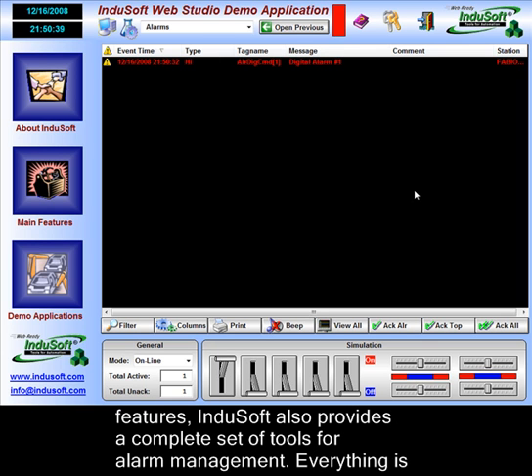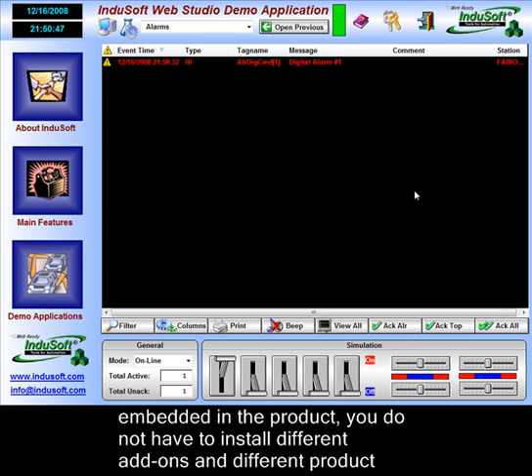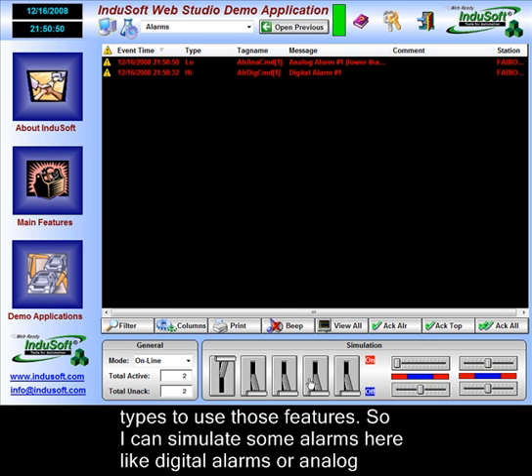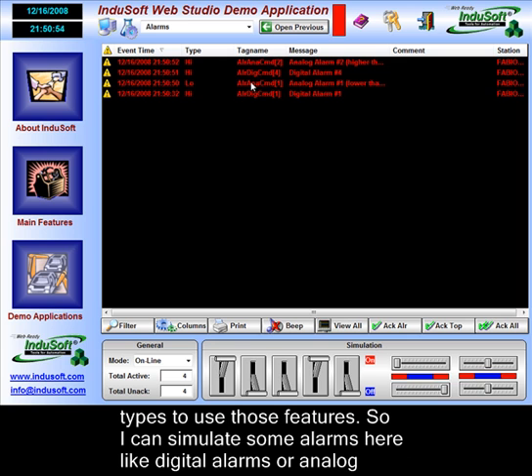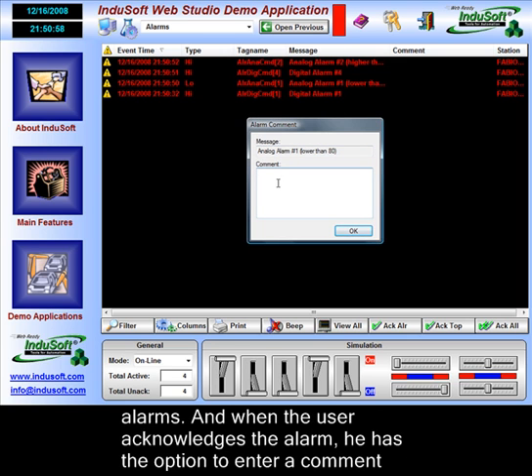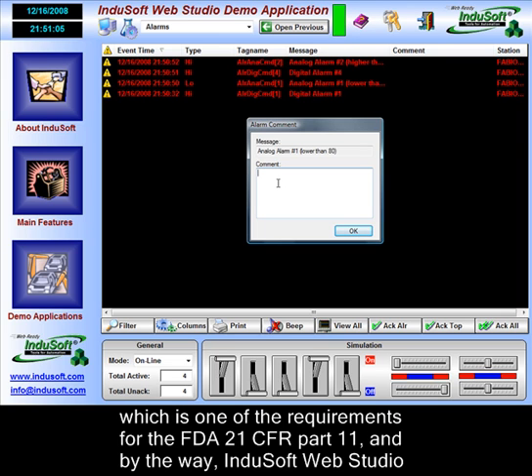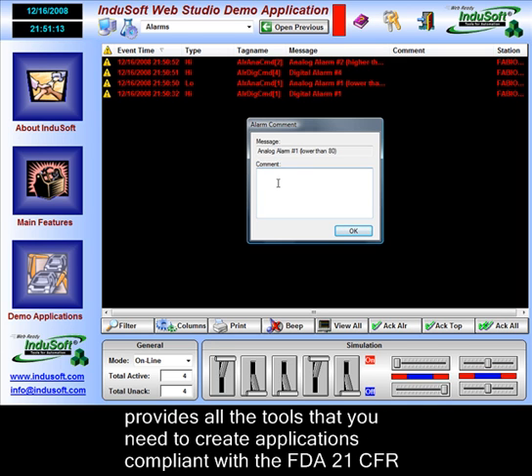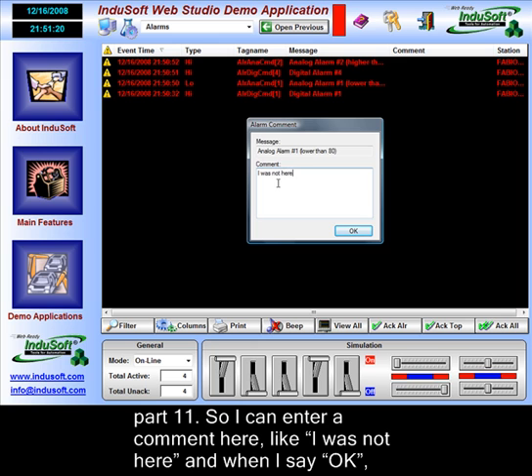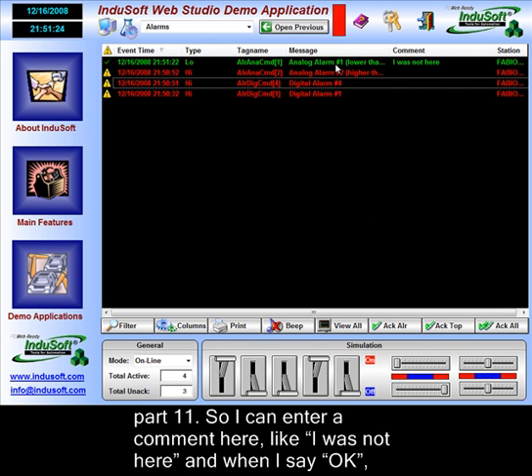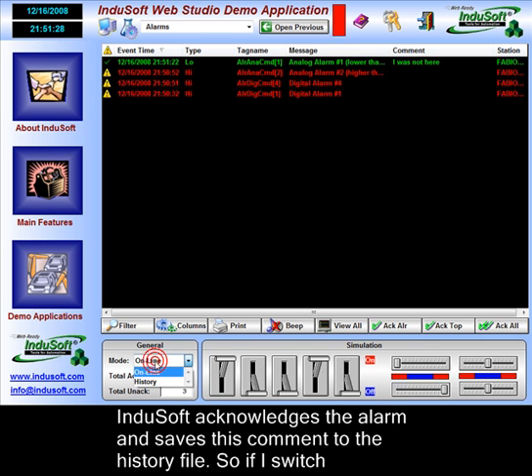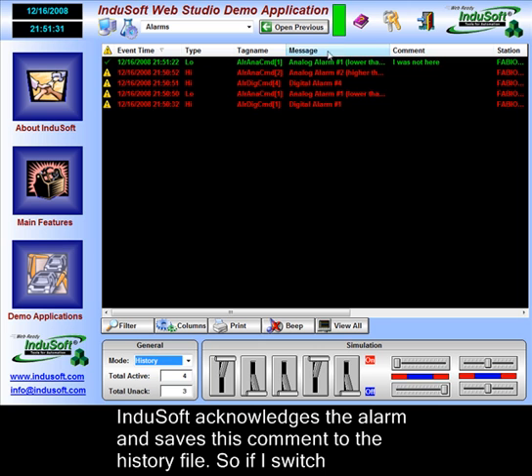In addition to the trending features, Indusoft also provides a complete set of tools for alarm management — everything is embedded in the product, with no separate add-ons needed. I can simulate some alarms here — digital alarms or analog alarms — and when the user acknowledges the alarm, he has the option to enter a comment, which is one of the requirements for the FDA 21 CFR Part 11. By the way, Indusoft Web Studio provides all the tools you need to create applications compliant with 21 CFR Part 11. When I enter a comment and click OK, Indusoft acknowledges the alarm and saves the comment to the history file.